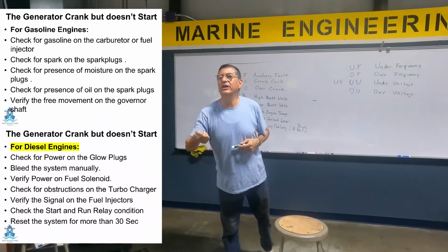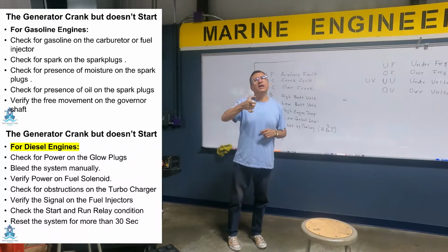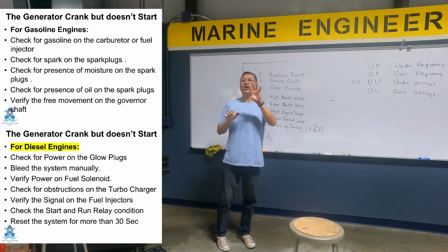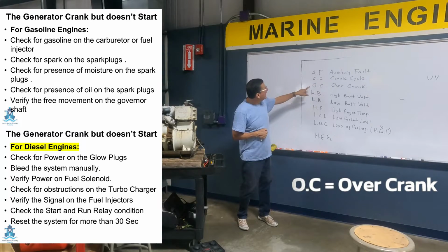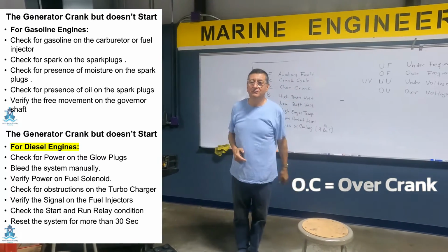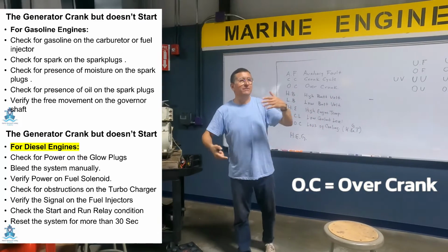We are going to simulate a couple of faults. One common fault is engine cranks but no start. When the engine cranks and does not start, what is the code in the display? Overcrank. And you know, you need to verify fuel, you need to verify spark, yeah?